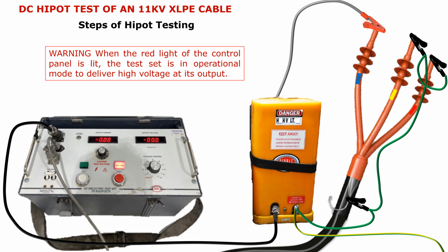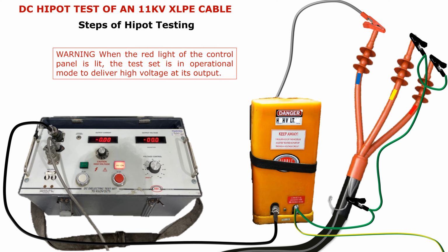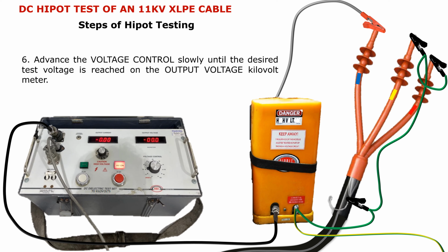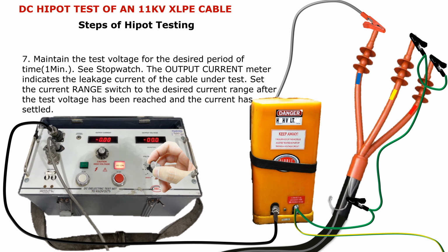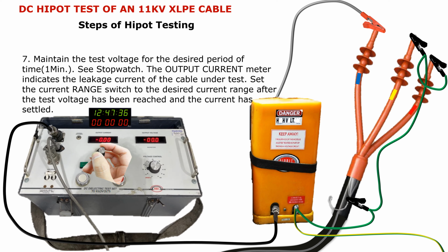Warning: when the red light of the control panel is lit, the test set is in operational mode to deliver high voltage at its output. Advance the voltage control in clockwise direction slowly until the desired test voltage is reached on the output voltage kilovolt meter. Maintain the test voltage for the desired period of time, 1 minute here. See stopwatch. The output current meter indicates the leakage current of the cable under test. Set the current range switch to the desired current range after the test voltage has been reached and current has settled.